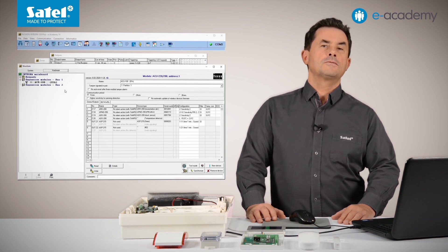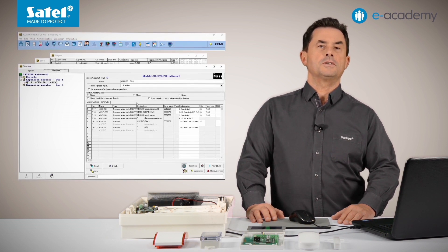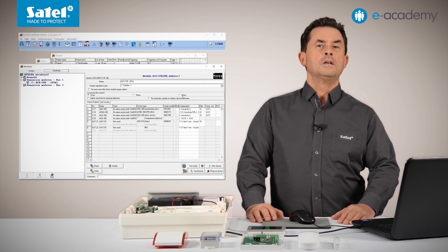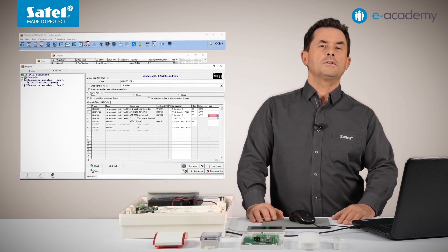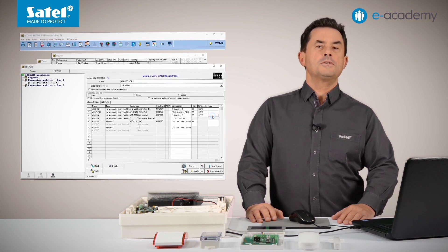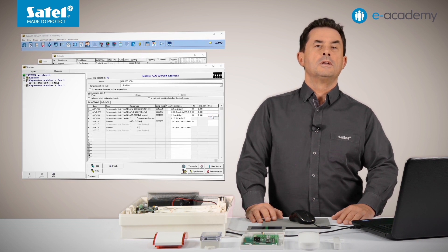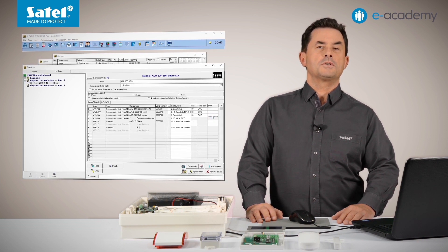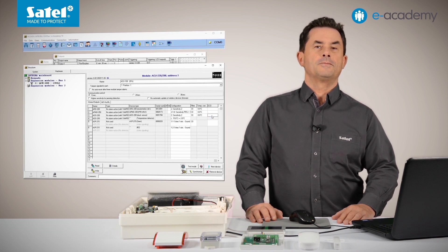The time delay may be 12, 24, or 36 seconds, or even 3 minutes when ECO mode is set. The thermal inertia of the detector itself must also be taken into account. All this should be kept in mind when configuring the heating operation.